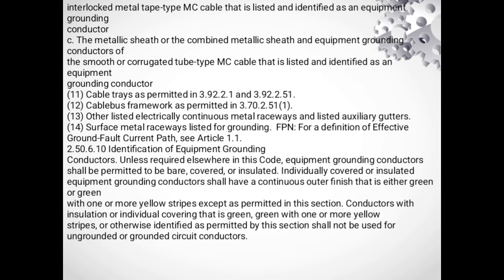Conductors unless required elsewhere in this code. Equipment grounding conductors shall be permitted to be bare, covered, or insulated. Individually covered or insulated equipment grounding conductors shall have a continuous outer finish that is either green or green with one or more yellow stripes, except as permitted in this section. Conductors with insulation or individual covering that is green, green with one or more yellow stripes, or otherwise identified as permitted by this section shall not be used for ungrounded or grounded circuit conductors.